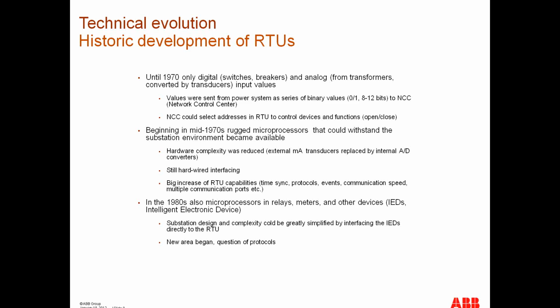So the IEDs now had direct contact with the RTU, sending all messages and data to the RTU, and the RTU had the possibility to act or send messages to the devices - a new area with new developments. At this time there was no common, vendor-independent protocol; every vendor used their own protocol for communication at the bay level, so it was quite difficult for the RTU to collect data coming from different protocols.